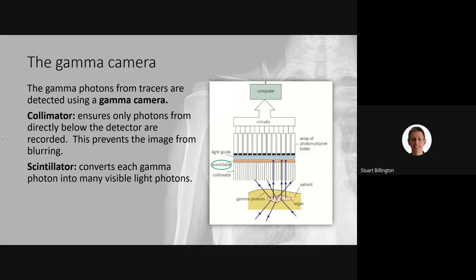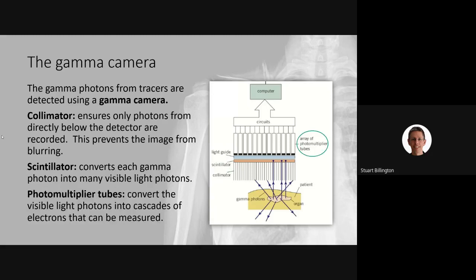The visible light photons from the scintillator travel in all directions, so a second collimating structure - a light guide, often using fiber optic cabling - directs them to the photomultiplier tubes. The photomultiplier tube is the core device that detects individual photons, converting them into an electrical signal, essentially answering how a camera turns a photon of light into an electrical signal.